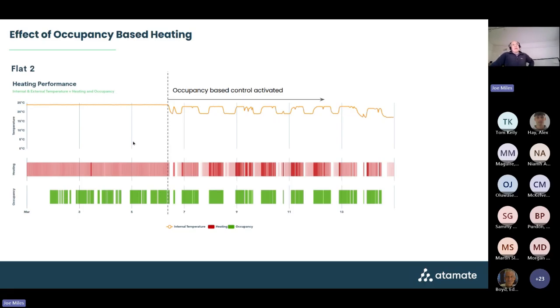Before this line, this is how a typical heating system would work - it's got no timing on it, it's just on permanently, but the system is holding the room at that temperature. Here we go into occupancy-based control, so now we're only turning on the heating when there's occupancy in that space. We're seeing really big savings by doing this - it's not unusual for us to see 30 to 40% savings in most non-domestic buildings that we're controlling.